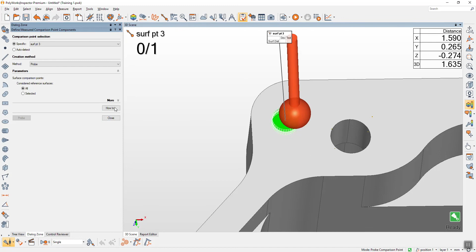So usually how do we define what is the okay radius size? Actually, it depends on the probe head. If your probe head is 6 mm, your radius should not be over 6 mm because you would still have too much tolerance. When you create the comparison point, this radius is 2.5, meaning diameter is 5. Diameter smaller than the probe is better. You can control the accuracy.